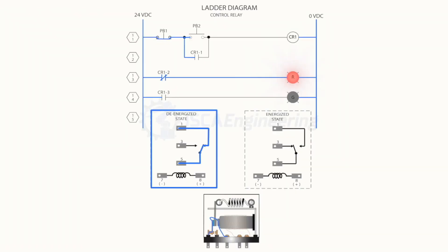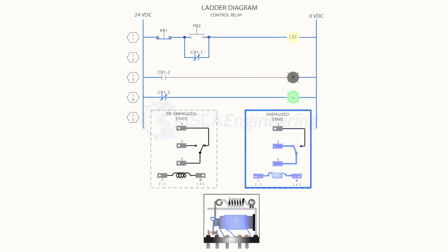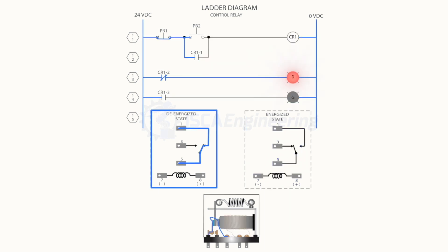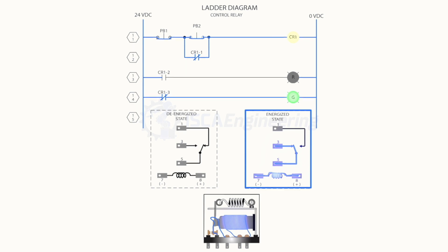In the de-energized state, the normally closed contacts allow current to flow through until the contacts change state. In the energized state, current flows through the normally open contacts until the contact states change. In the example, when de-energized the red indicating light will be on. After the coil is energized, the red indicating light will go off and the green indicating light will come on until the coil is de-energized.